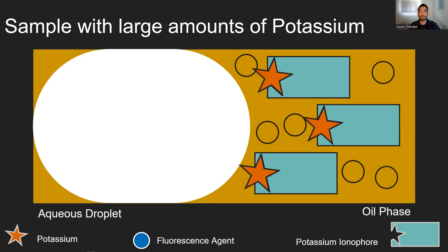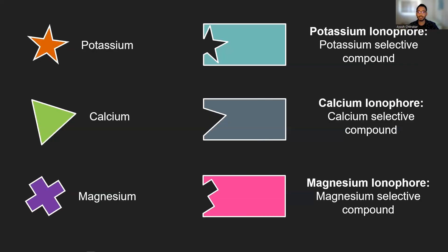So we can use this potassium selective oil to detect potassium. But how do we change the system to be able to detect other electrolytes such as calcium or magnesium? We can simply change the ionophore that we're using. This is the chemical that can selectively bind to whatever electrolyte that we want. So in this case, we can use the calcium ionophore to measure calcium and a magnesium ionophore to measure magnesium.